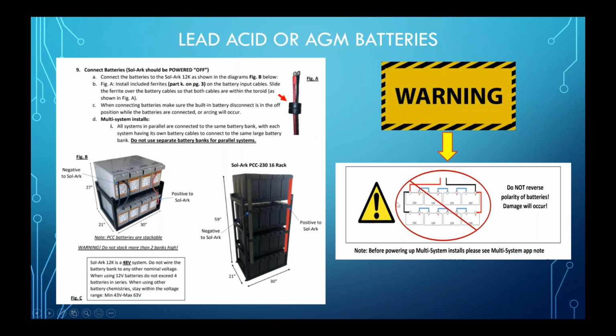And the other thing I would mention is over here, where you have the big yellow triangle with the black exclamation point in it, trying to visually draw your attention to that. This is something that's very serious. When you are connecting batteries to the Sol-Ark, pay careful attention to your terminal, your polarity. Don't connect the red wire to the black one, and don't connect the black one to the red one. If you reverse polarity and you're hooking up the positive to the negative and the negative to the positive, it will damage the Sol-Ark. So very, very serious. Please pay careful attention to the polarity of the battery cables when you are connecting the battery.